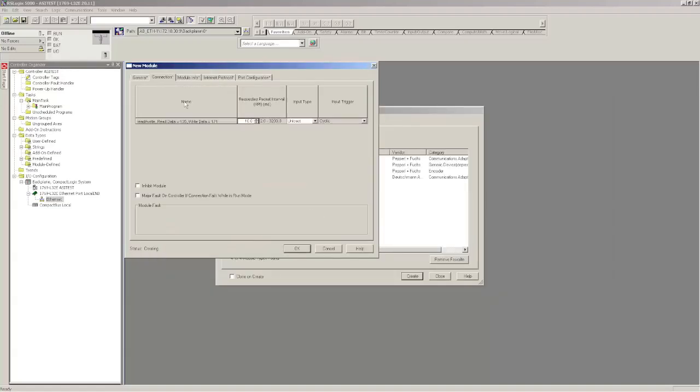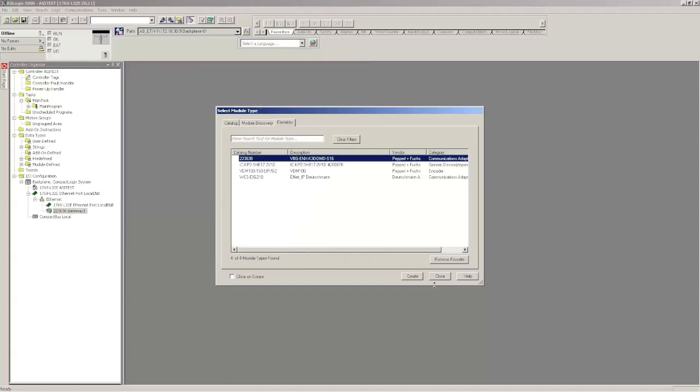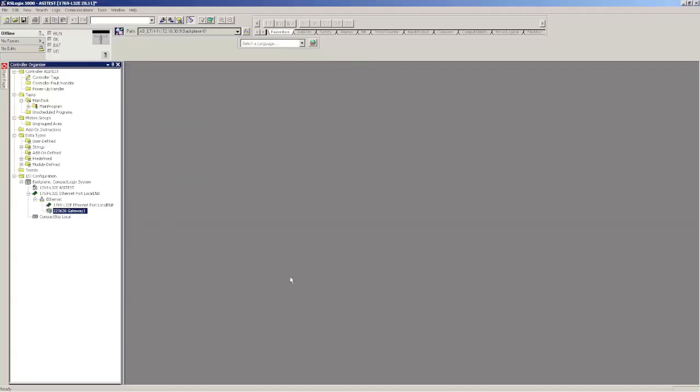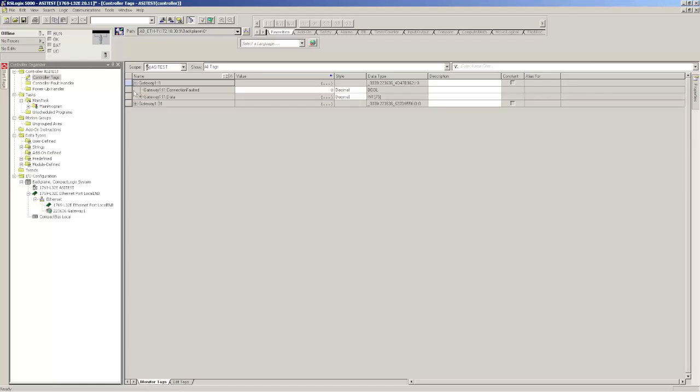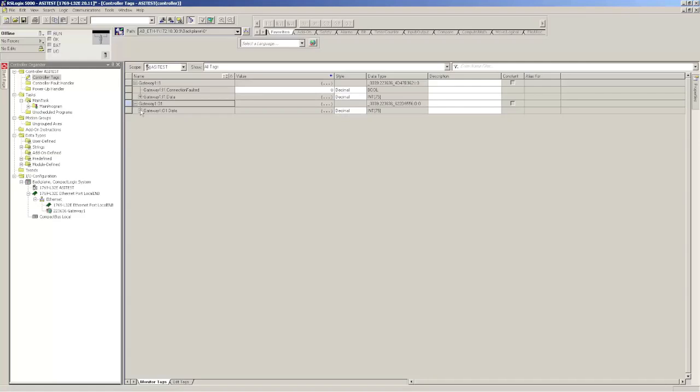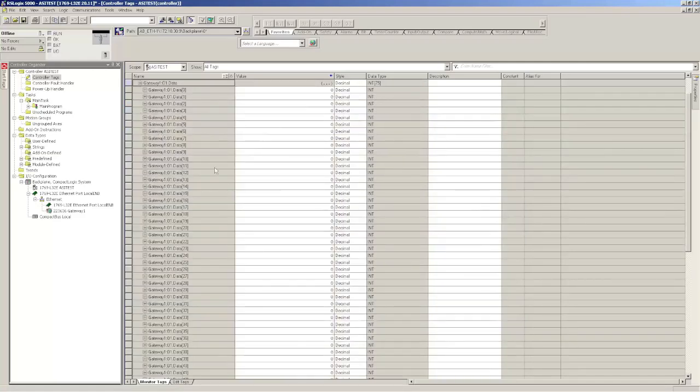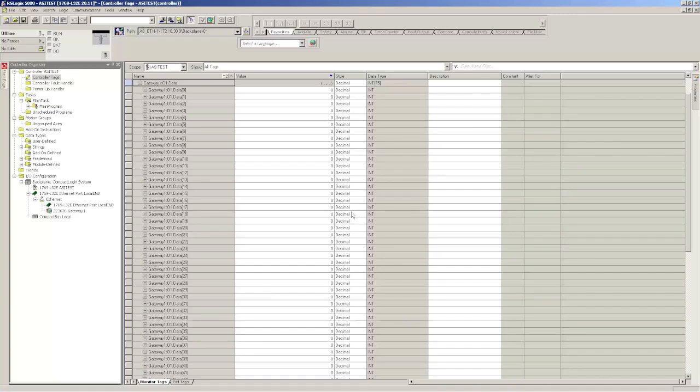Everything looks good. You can see the RPI right here. You don't have to change that if you don't want. And then you've got the Input Type Unicast. That's fine. You can see the AS Interface Gateway is right here called Gateway 1. If we go into Controller Tags, you'll see now your outputs are directly mapped and your inputs are directly mapped. On the input data, it'll tell you whether the connection is faulted or not online by this single Boolean variable called Connection Faulted. But if you notice, you just get one large array of data. You don't know exactly where the I.O. modules are. You don't know what they're called.